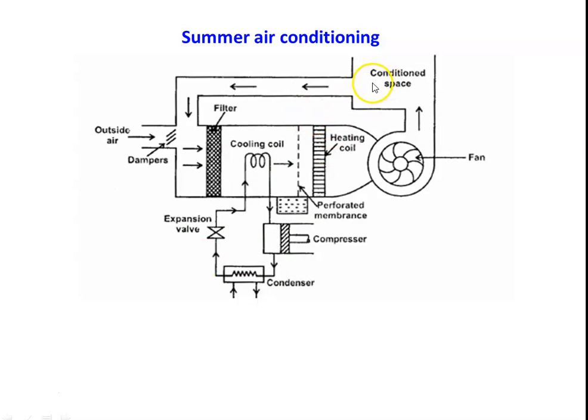As usual, the recirculated air is entering here. Outside air using the damper is entering here. These two airs go through the filter where the dust particles are removed. Then it flows over the cooling coil. So the cooling coil, look at this. This is the evaporator coil of the refrigeration system. In the refrigerator, we have the evaporator, compressor, condenser, expansion valve, and then the refrigerant is circulated.